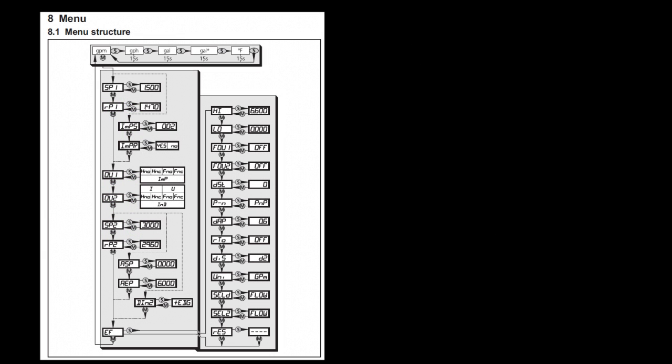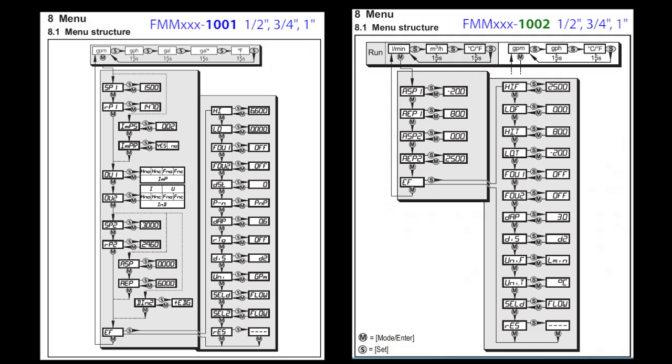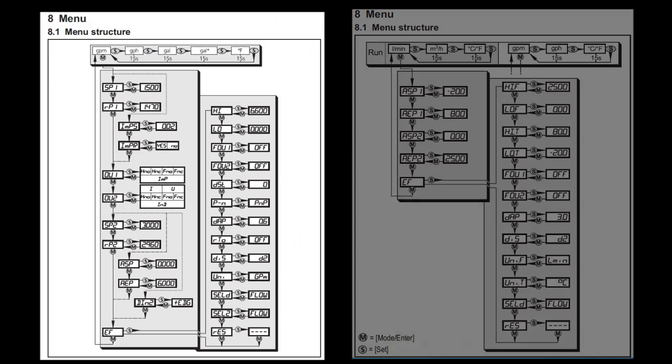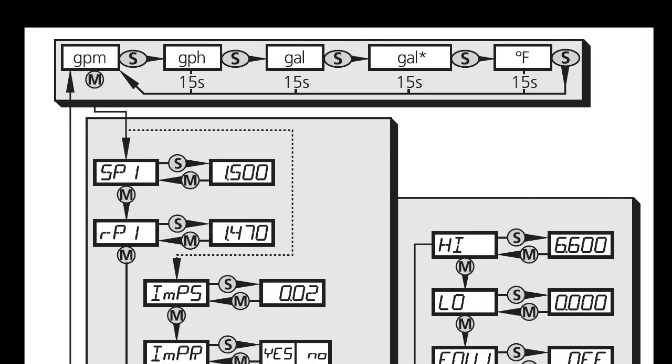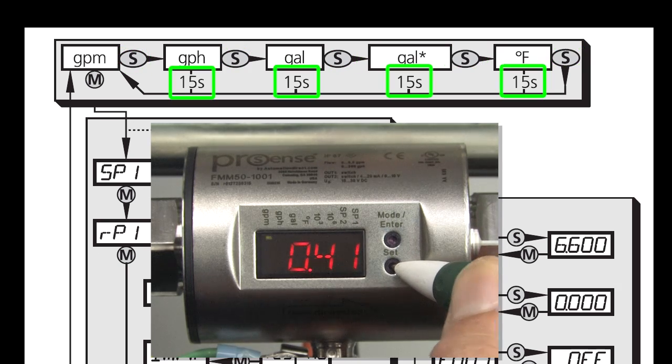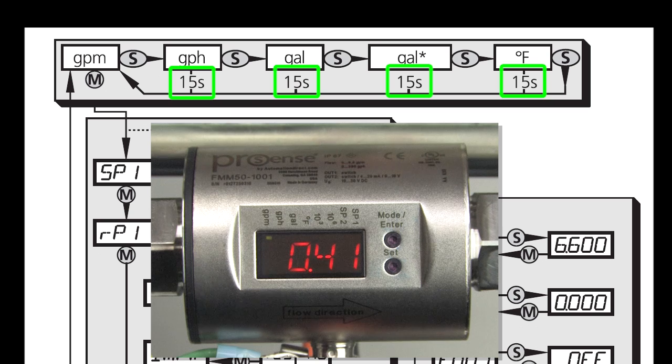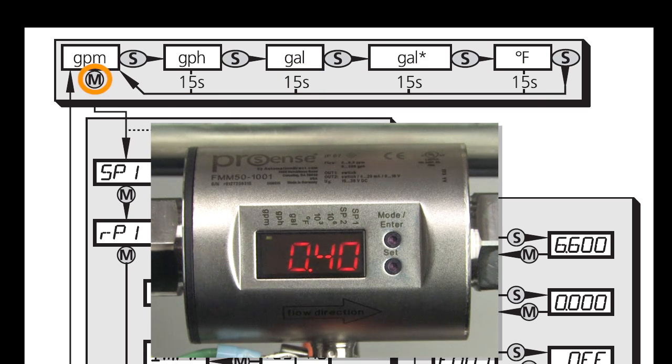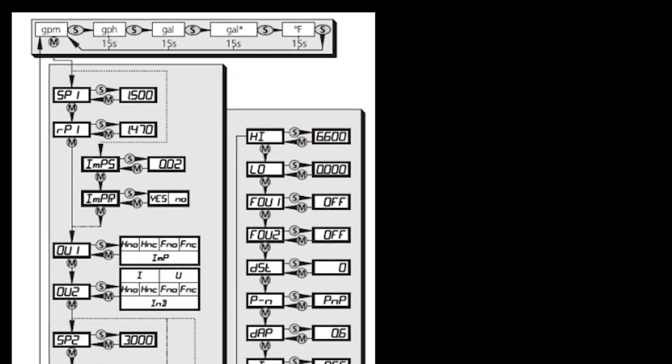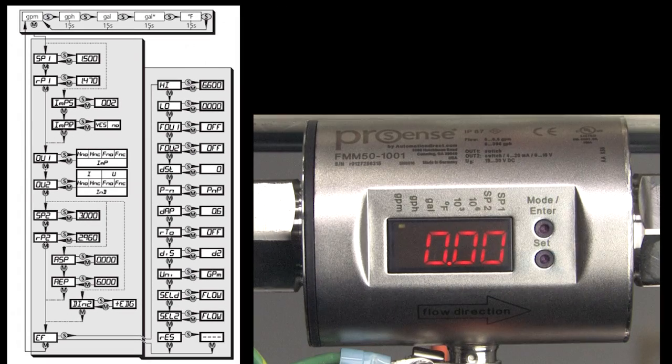To configure the flowmeter, go to chapter 8 of the user manual where you'll find a parameter menu like this one. We're using the smaller 1001 series flowmeter in this video. The 1002 version is very similar but it has fewer options since it only has two analog outputs. The chart is telling me to press the S button to cycle through the display options and each of those will fall back to the default display after 15 seconds. And the M or mode button drops us down into parameter setting mode.